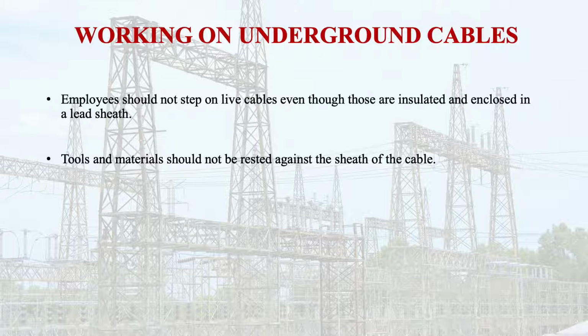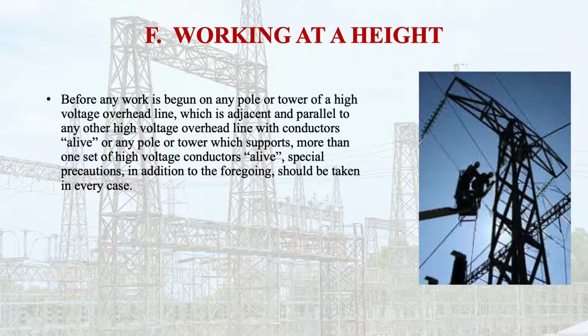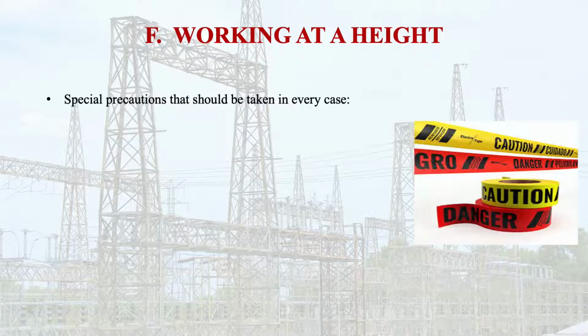Now let us discuss working at a height. What safety precautions or safety instructions apply for this? Before any work is begun on any pole or tower of a high voltage overhead line which is adjacent and parallel to any other high voltage overhead line with conductors alive, or any pole or tower which supports more than one set of high voltage conductors alive, the following special precautions, in addition to the foregoing, should be taken in every case.